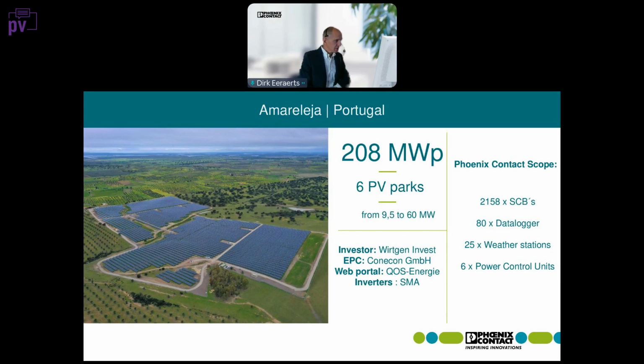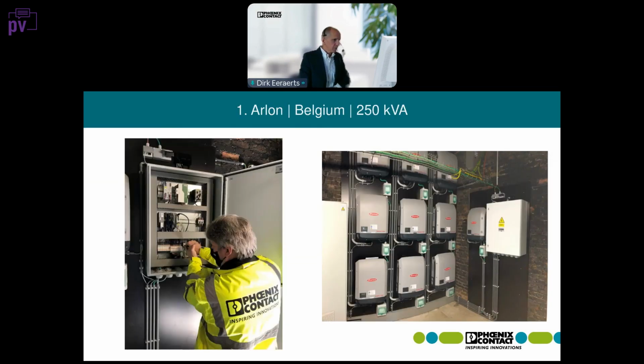I am myself connected to the Belgium office, and in Belgium we have a lot more small sites. A lot of them are rooftop sites with local consumption. And a typical example of such a plant is what you see here. So on the left-hand side, you see the cabinet that we would provide. See if this marker works, but so this is the power control unit with the software integrated. What else you see is power supply, UPS, and communication devices. And so from here we communicate with the RTU of the DSO, and we communicate with the inverters and with the switchgear.